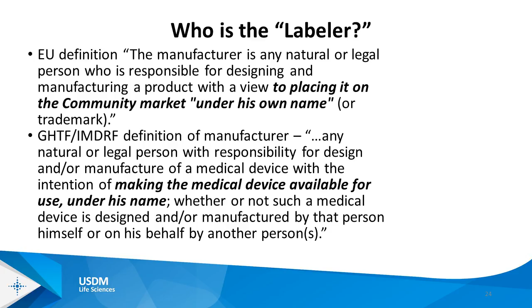The other issue that we talk about is really how your products are actually labeled and packaged. One of the issues that comes up, and again, hopefully everyone understands that the UDI goes on the label of the device. Label is a regulatory concept. Label is where other regulatory information goes. So hopefully everyone knows where their label is, what that looks like, and that's where UDI goes. This is not just a supply chain activity. We often hear folks talk about the orderable unit or the shippable unit. I'll just put the UDI on the shippable unit. Well, no, these are not concepts that you're going to see anywhere in the UDI rule. They talk about the label, goes on the label, and as you put that device into higher levels of packaging, you will put a UDI on those higher levels of packaging. So be sure that you understand where the label is, what that looks like, and that's where UDI goes, as well as the higher levels of packaging, however you decide to manage that.